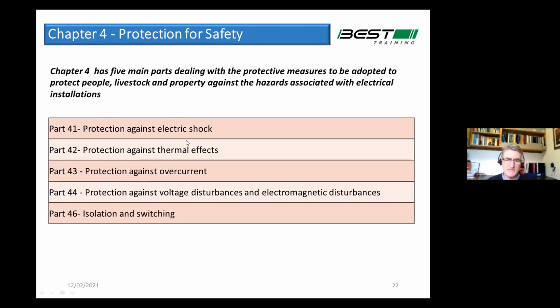Then protection against thermal effects covers thermal effects like burns, but more importantly, fires from electrical installations. And it introduces a new recommended practice of installing AFDDs, arc fault detection devices. And you're going to be seeing more of these. They are recommended in places with sleeping accommodation and places where there's a risk of loss of cultural heritage, for example, a museum, an art gallery, something like that. They're recommended there, or buildings that have combustible materials stored, or the building itself is of combustible construction, like a timber structured house or thatched roof, something like that.